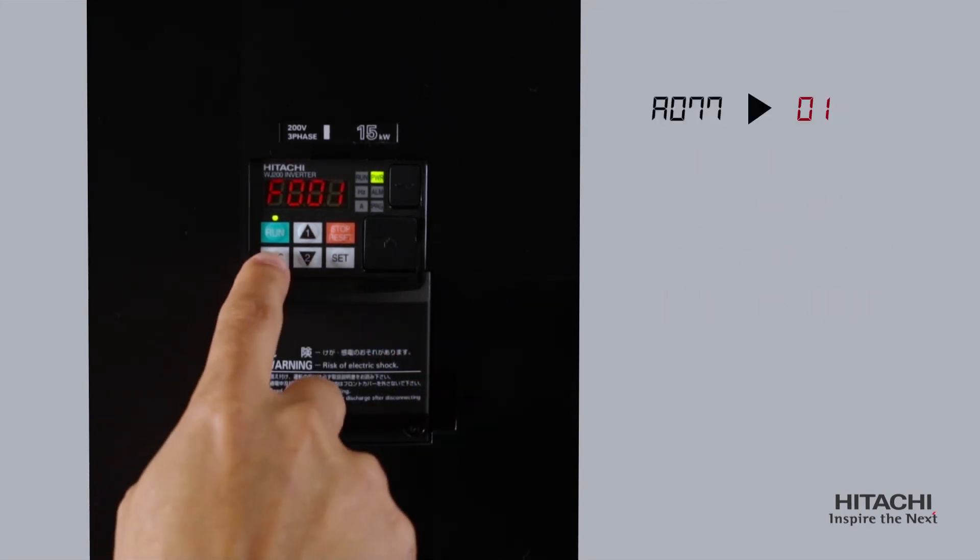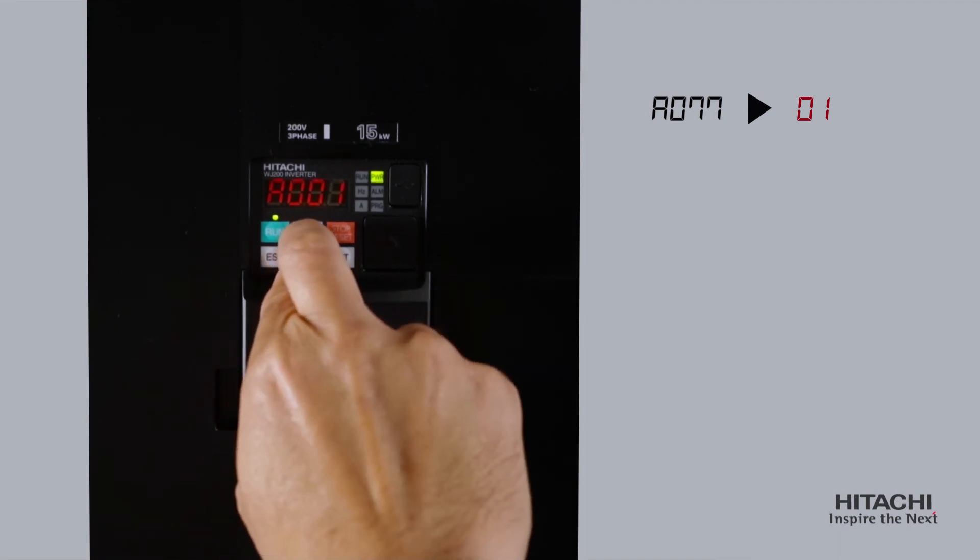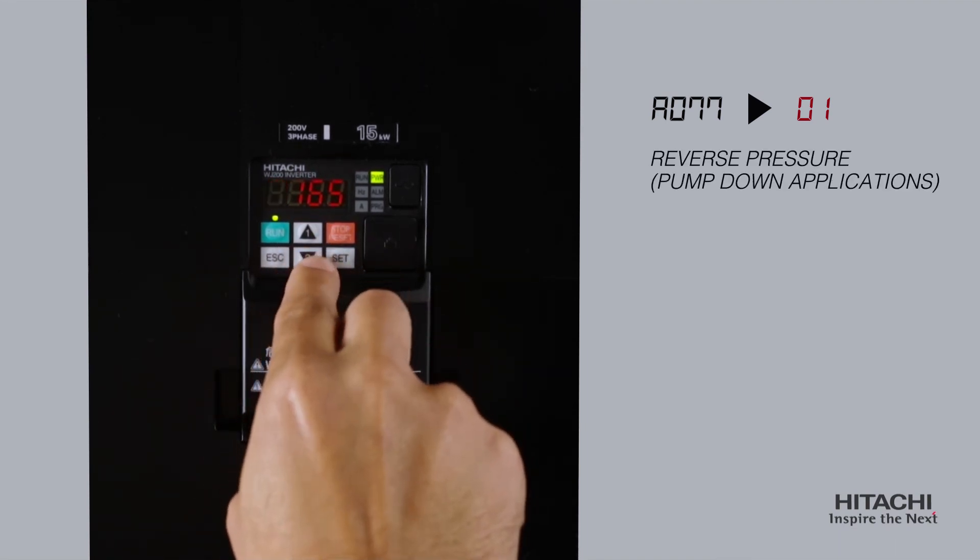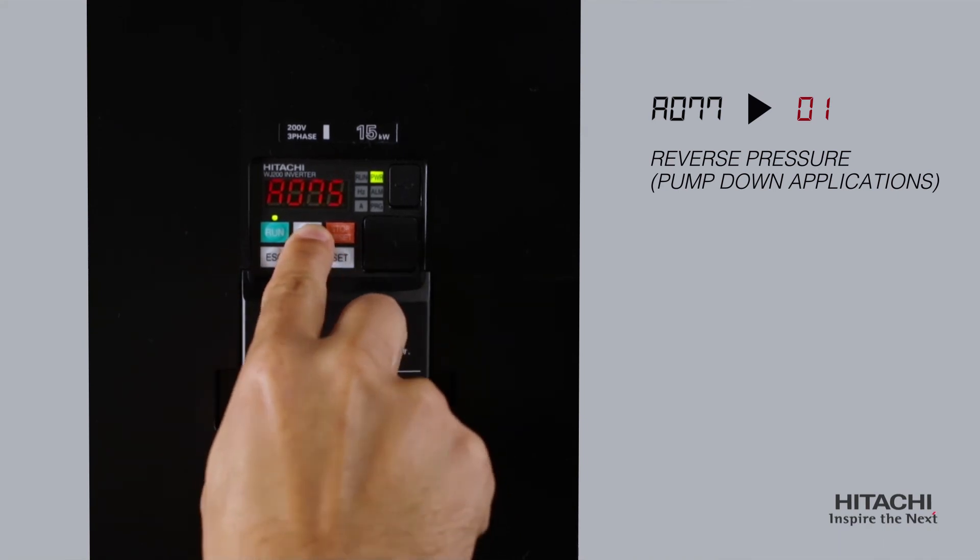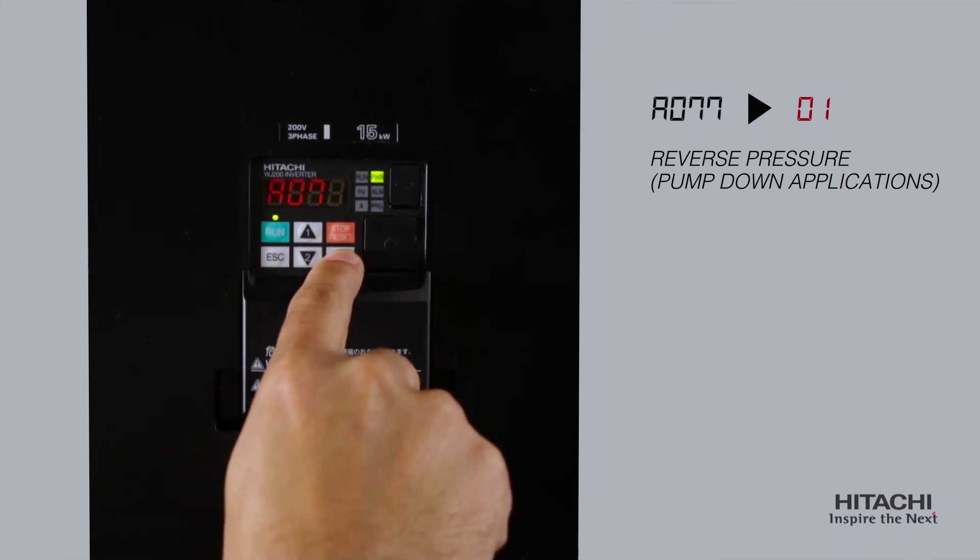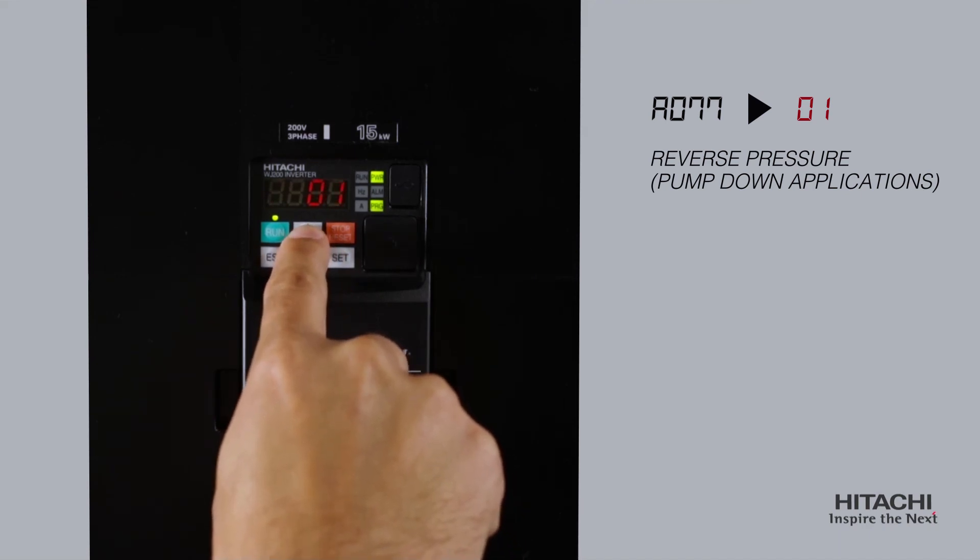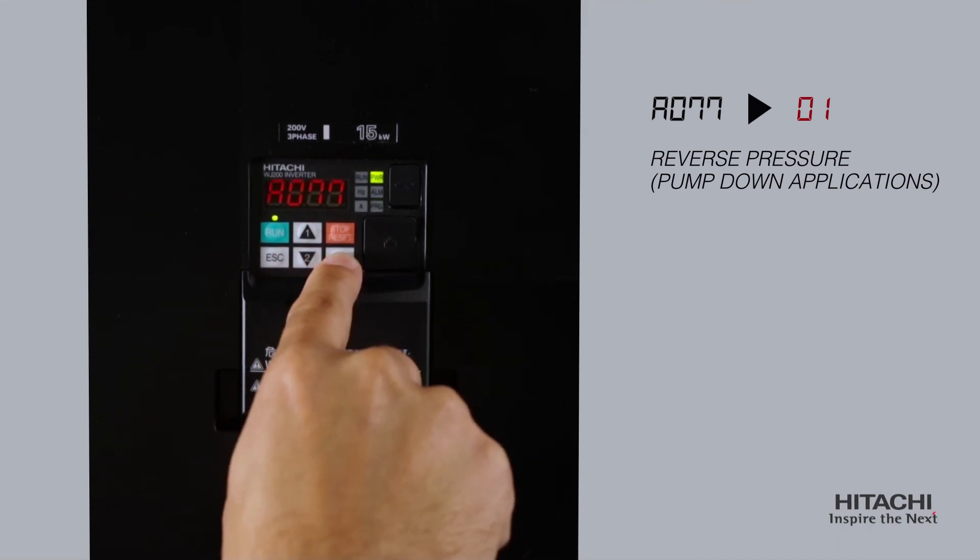Set A77 to 01 to reverse the pressure or for pump down applications. This will cause the inverter to operate in a mode required to keep a water level down to a set point in a catch basin system, such as a retaining pond.